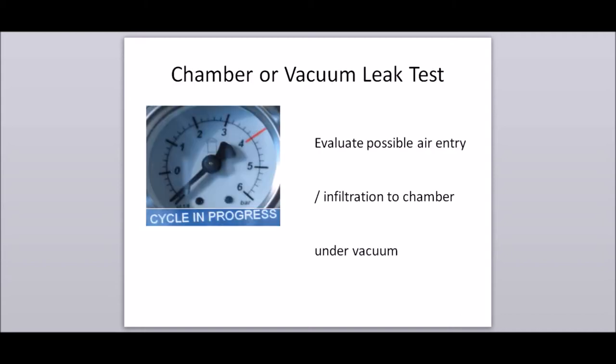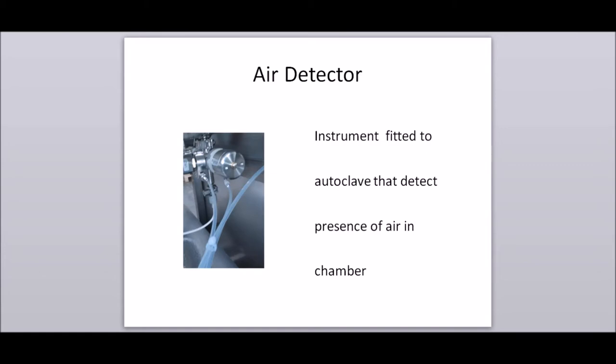Chamber leak test, or vacuum leak test: a test conducted to evaluate possible air entry or infiltration into a chamber under vacuum. Air detector: an instrument fitted to an autoclave that detects the presence of air in the chamber. Air may be ingressed due to a chamber leak or steam quality.